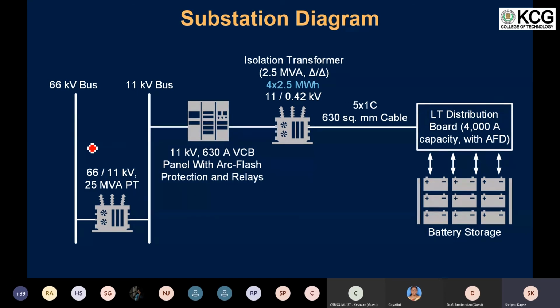So mostly you would find it either on an 11 kV system or a 33 kV system. And in some cases, wherein the photovoltaic generation is at a large rating, for example 30 megawatt, 40 megawatt or 50 megawatt, these kinds of grid stations are also connected to the 110 kV and 132 kV level systems. In any case, you are still going to connect all your photovoltaic cells or battery storage equipment on the LT system only, where the hazard of arc flash is also pretty evident.